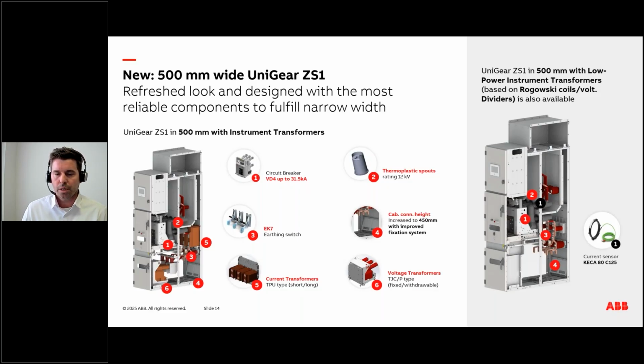When we look into the low power instrument transformers version of the panel, the panel accommodating the medium voltage sensors, as Unigear is known for, we can accommodate up to 2 sets of current sensors, which are based on the Rogowski coil principle, and also up to 2 sets of voltage sensors. One of them can be installed in the busbar compartment for busbar voltage measurement, and the second can be installed in the cable compartment for cable voltage measurement.